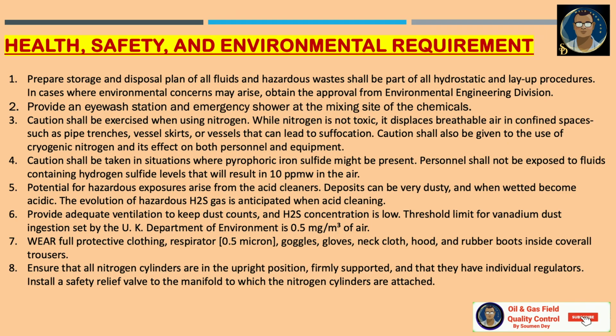Potential for hazard exposures arise from acid cleaners. Deposits can be very dusty and when wetted become acidic. The evolution of hazardous H2S gas is anticipated when acid cleaning. Provide adequate ventilation to keep dust counts and H2S concentration low. All workers for chemical cleaning shall wear full protective clothing, respirator, goggles, gloves, neck cloth, hood, rubber boots, and inside coverall and trousers. Ensure that all nitrogen cylinders are in an upright position, firmly supported, and have individual regulators. Install a safety relief valve on the manifold to which nitrogen cylinders are attached.